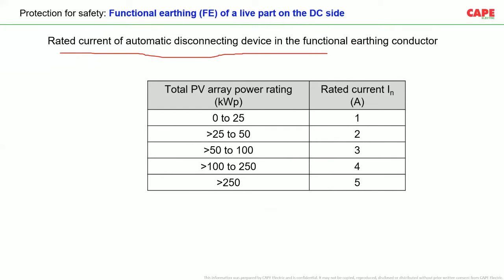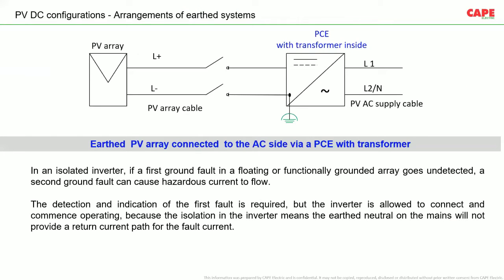Rated current of the automatic disconnection device in the functional earthing conductor. That means the functional earthing wire has a fuse. The fuse rating is based on the PV array size in kWp. For example, 0 to 25 kilowatt, the fuse is 1 amp. 100 to 250 kilowatt, it is 4 amps. More than 250 kilowatt, 5 amps. 25 to 50, it is 2 amps. Basically, this kind of fuse is implemented in this location.